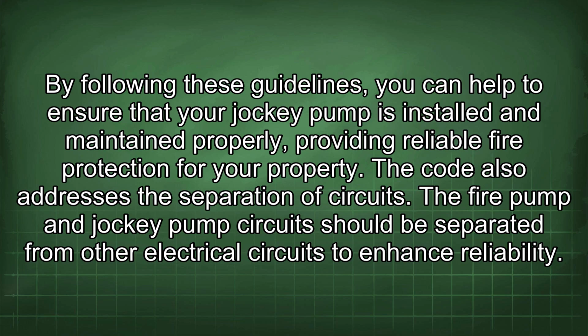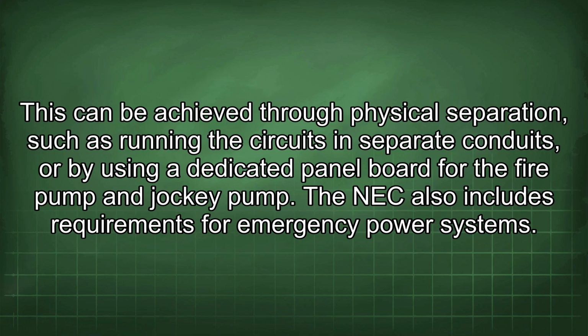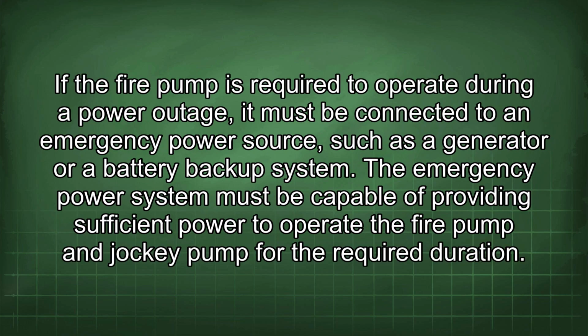The code also addresses the separation of circuits. The fire pump and jockey pump circuit should be separated from other electrical circuits to enhance reliability. This can be achieved through physical separation, such as running the circuits in separate conduits, or by using a dedicated panel board for the fire pump and jockey pump. The NEC also includes requirements for emergency power systems. If the fire pump is required to operate during a power outage, it must be connected to an emergency power source, such as a generator or battery backup system.